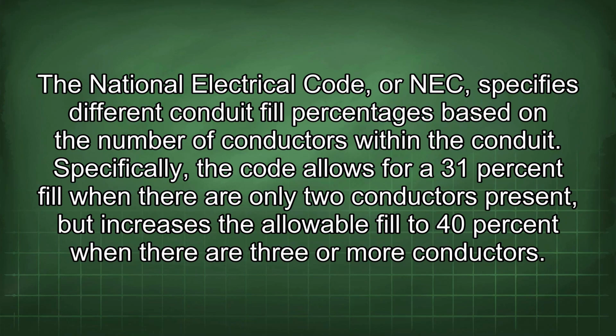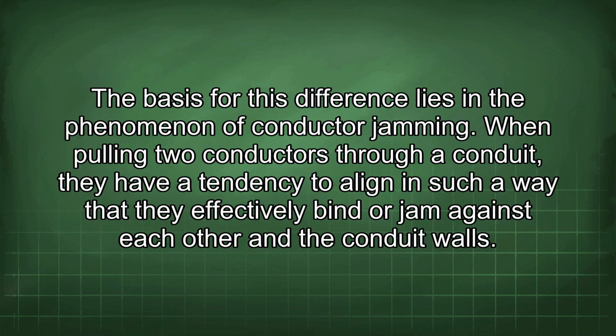The National Electrical Code, or NEC, specifies different conduit fill percentages based on the number of conductors within the conduit. Specifically, the code allows for a 31% fill when there are only 2 conductors present, but increases the allowable fill to 40% when there are 3 or more conductors. The basis for this difference lies in the phenomenon of conductor jamming.